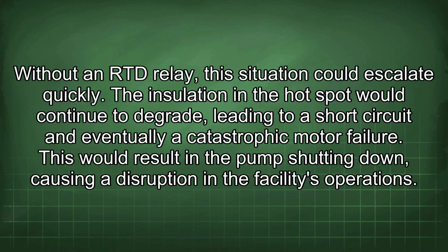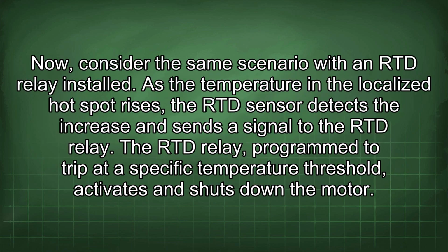Without an RTD relay, this situation could escalate quickly. The insulation in the hotspot would continue to degrade, leading to a short circuit and eventually a catastrophic motor failure. This would result in the pump shutting down, causing a disruption in the facility's operations. Now, consider the same scenario with an RTD relay installed.